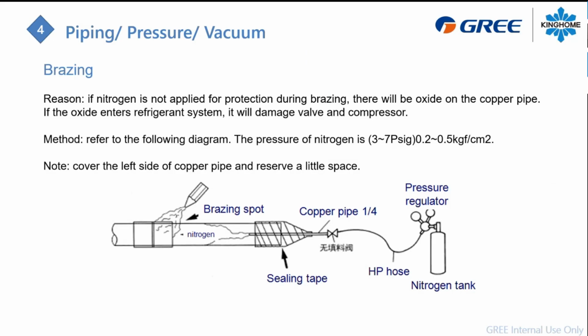When you do your brazing, you need to apply nitrogen while you are brazing the spot, because the heat will create some scale, some oxide. You can see it on the outside of the piping, but it will be created inside of it too. So make sure you flow around 5 psi of nitrogen the entire time you are brazing your piping. You need to flow the nitrogen always when brazing the piping. This is really, really, really important.